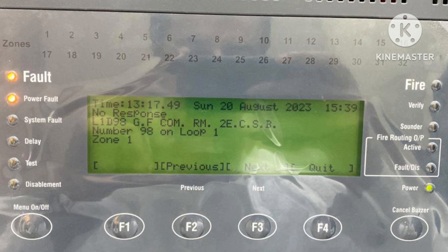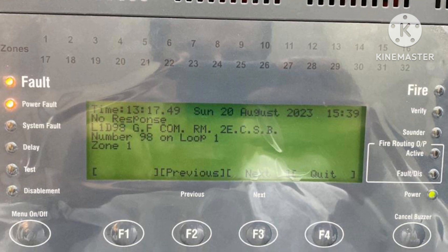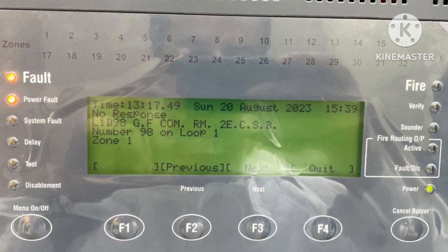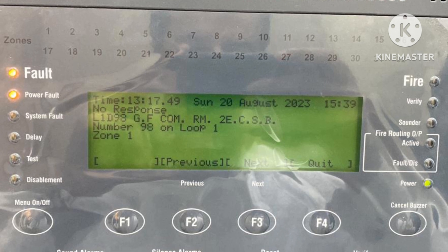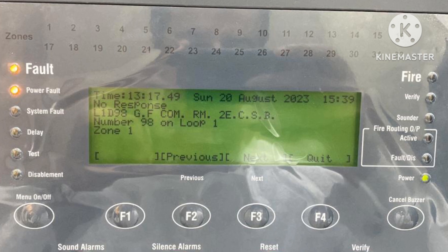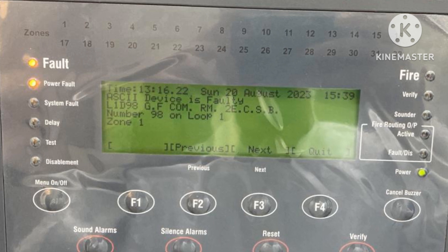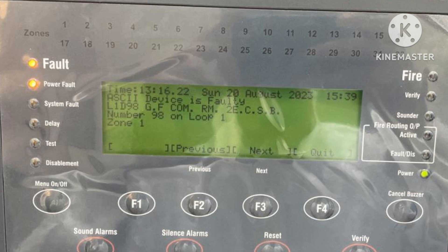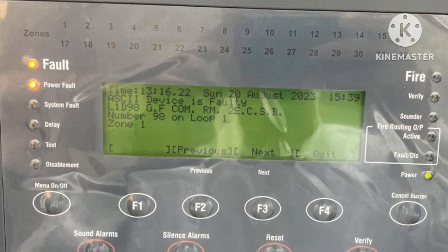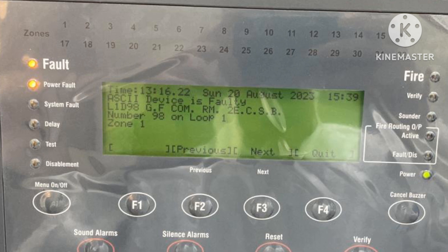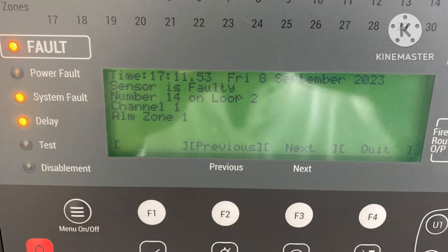The first trouble here is 'no response' — loop 1, device number 98, ground floor communication room. Device number 98 on loop 1 is not responding. If you get this type of fault, it means the loop-powered repeater panel or mimic panel is not responding. The ASCII device is faulty and there is also a power fault. You can see the left-side LED — the repeater panel is off. Go check and power it on, or reset it.